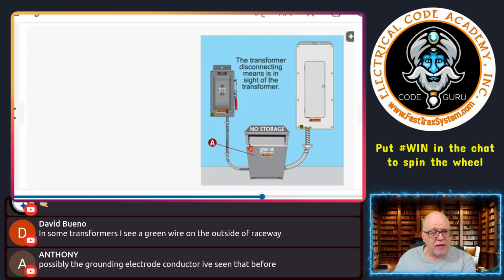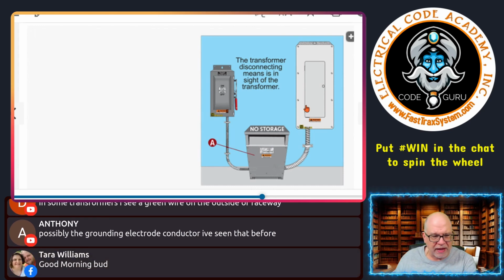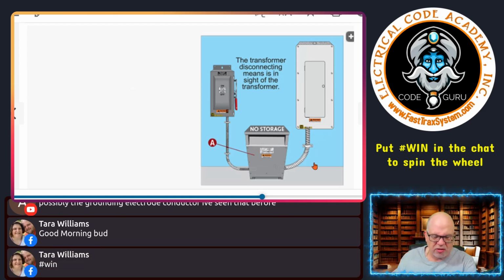Okay. One of the things to remember is that you could also have a solid raceway here, not likely, but you could have an EMT or something like that, and then you wouldn't have to pull a wire type supply side bonding jumper through here, because you could use the raceway if it is non-flexible. I do not see that ever. It's very rare for me to ever see anybody run pure something like an EMT over to it. Okay, usually it's a small section or something like that.